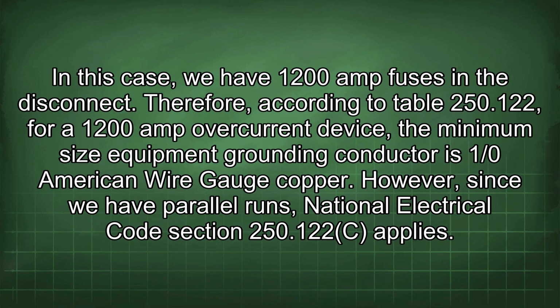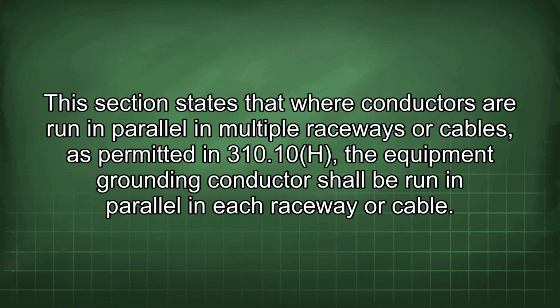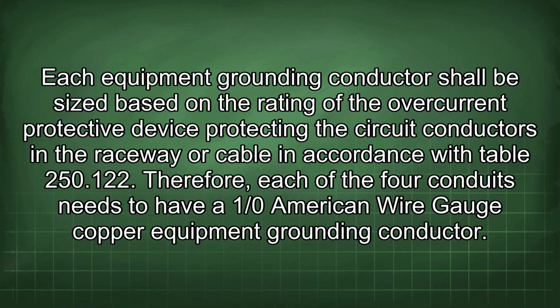250.122c applies. This section states that where conductors are run in parallel in multiple raceways or cables, as permitted in 310.10h, the equipment grounding conductor shall be run in parallel in each raceway or cable. Each equipment grounding conductor shall be sized based on the rating of the overcurrent protective device protecting the circuit conductors in the raceway or cable in accordance with table 250.122. Therefore, each of the 4 conduits needs to have a 1/0 American wire gauge copper equipment grounding conductor.